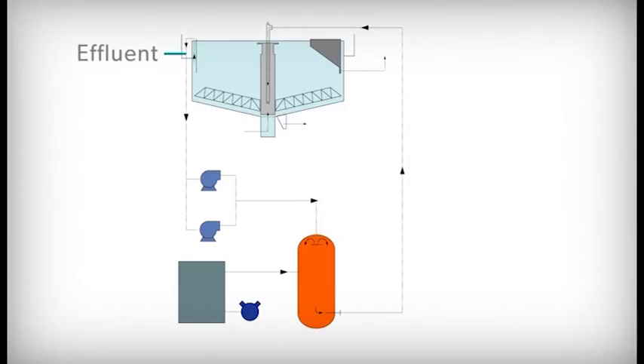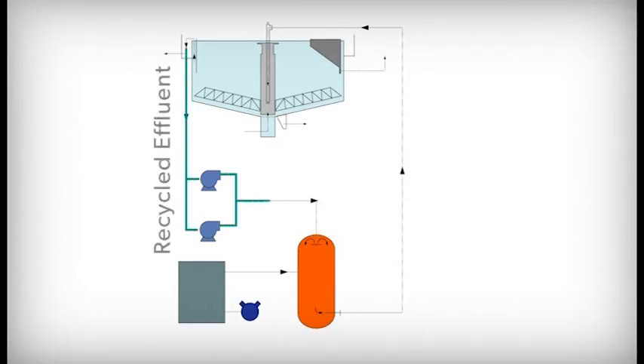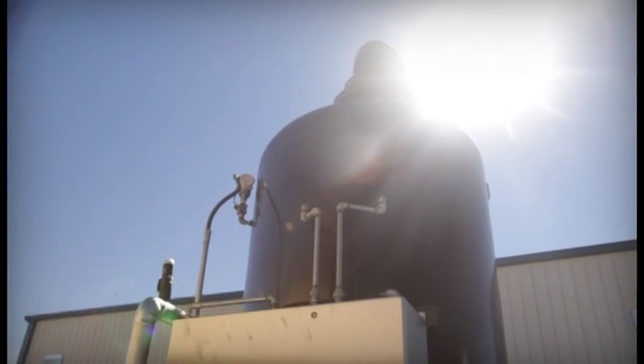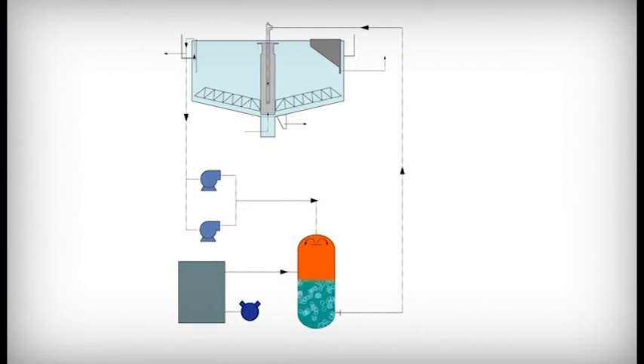A typical DAF system is designed to recirculate a portion of the clarified effluent through a pressurization system by means of a centrifugal recycle pump. The recycled effluent is pumped into an air saturation tank where compressed air is dissolved into the flow under pressure. The air saturated recycle is then fed under pressure to the DAF tank where it thoroughly mixes with the DAF influent flow.